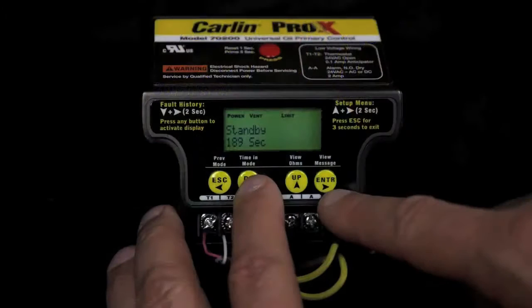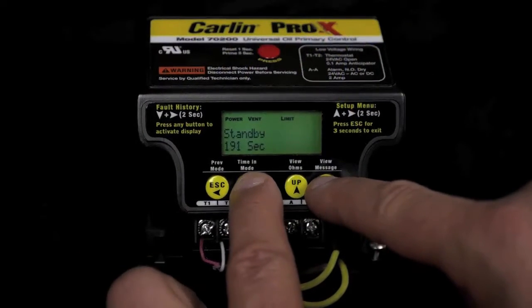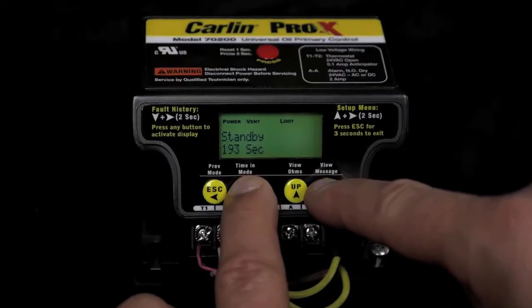Troubleshooting with the ProX 70200 is a breeze. The built-in diagnostics of the ProX stores all operating history and information from the last 50 fault cycles. With this extensive stored history in common sense codes and language, it's easy to track and diagnose a burner fault and its cause.